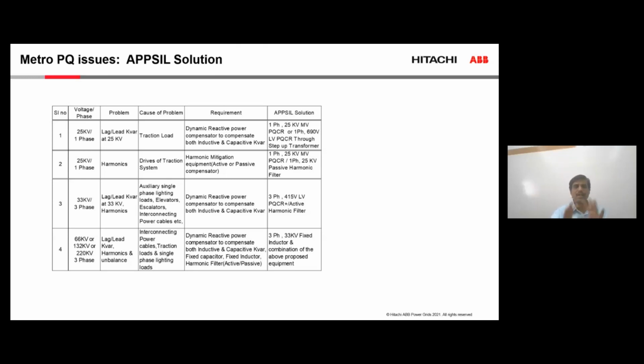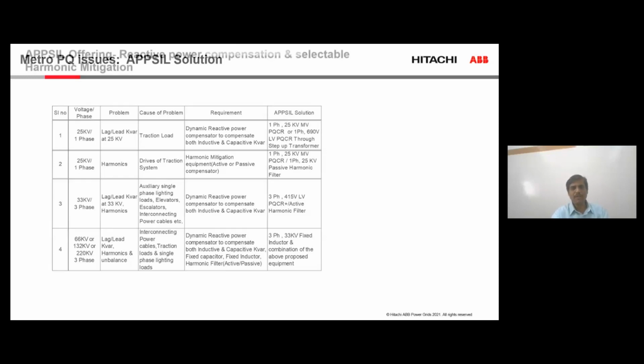So what in a nutshell I'm trying to say is that we normally study the different problems in a metro occurring at different voltage levels, 25 kV, 33 kV, 66 kV, and we apply engineered optimal power quality solutions at each of these bus levels, depending upon the situation, so that at the point of common coupling we have the best power quality and the least electricity bill. So that's basically the aim of the solutions.